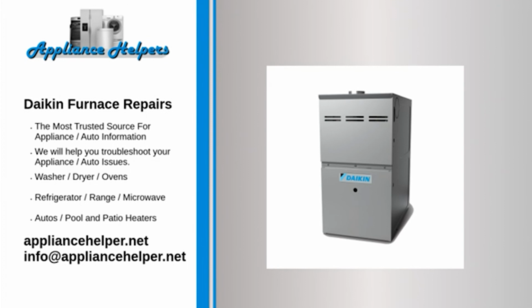The furnace makes loud noises. A noisy furnace is most often the result of the furnace being a single-stage model that runs at high capacity all the time, so it's going to be loud. A bad bearing in the draft motor or the blower motor must be replaced. A leak in the furnace cabinet, sheet metal plenum, or ductwork near the furnace must be tightened. A dirty filter can also cause whistling.